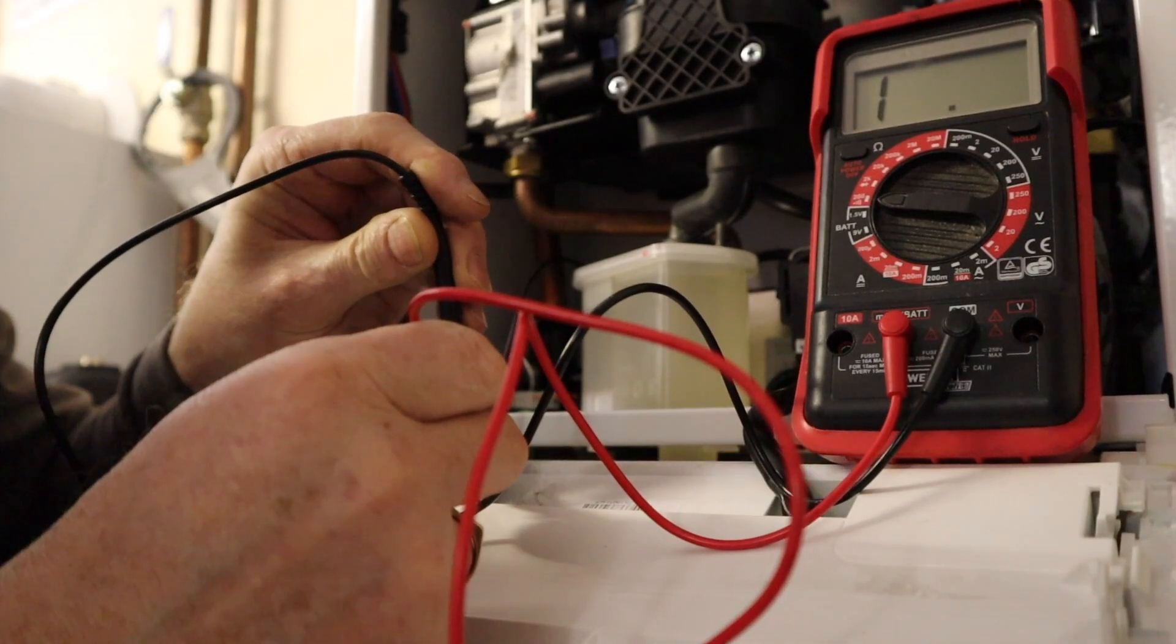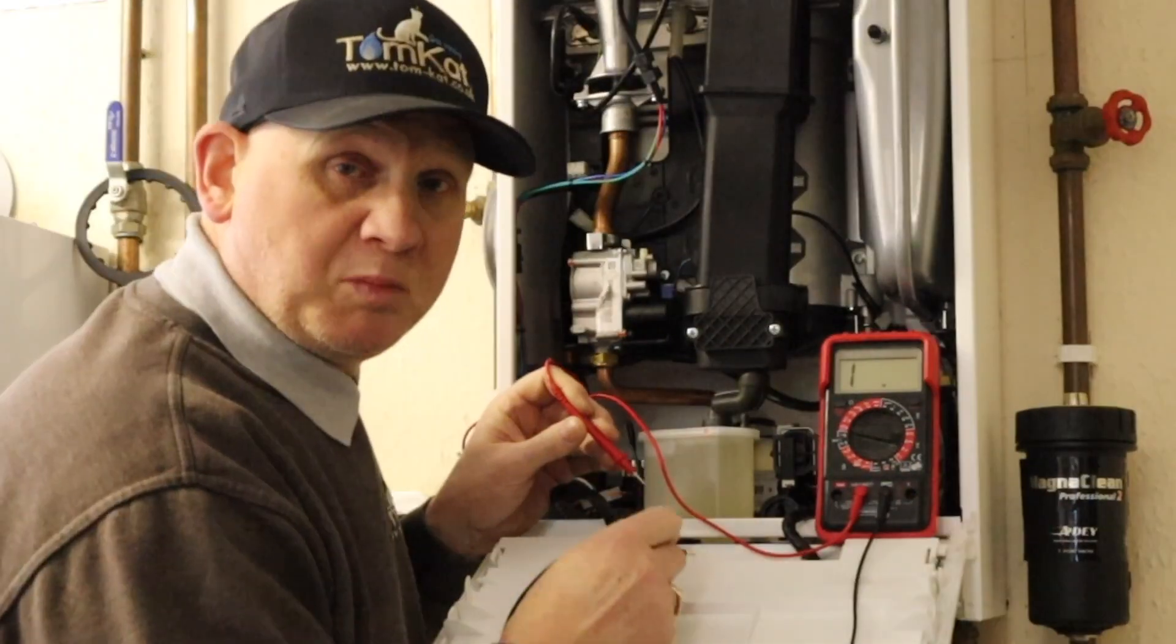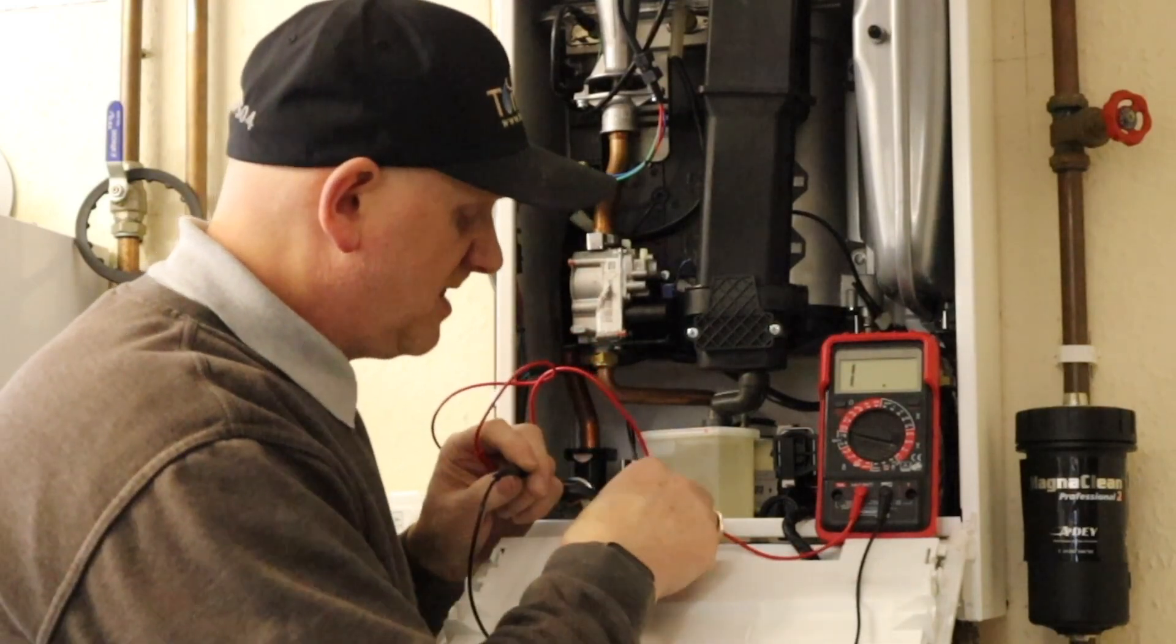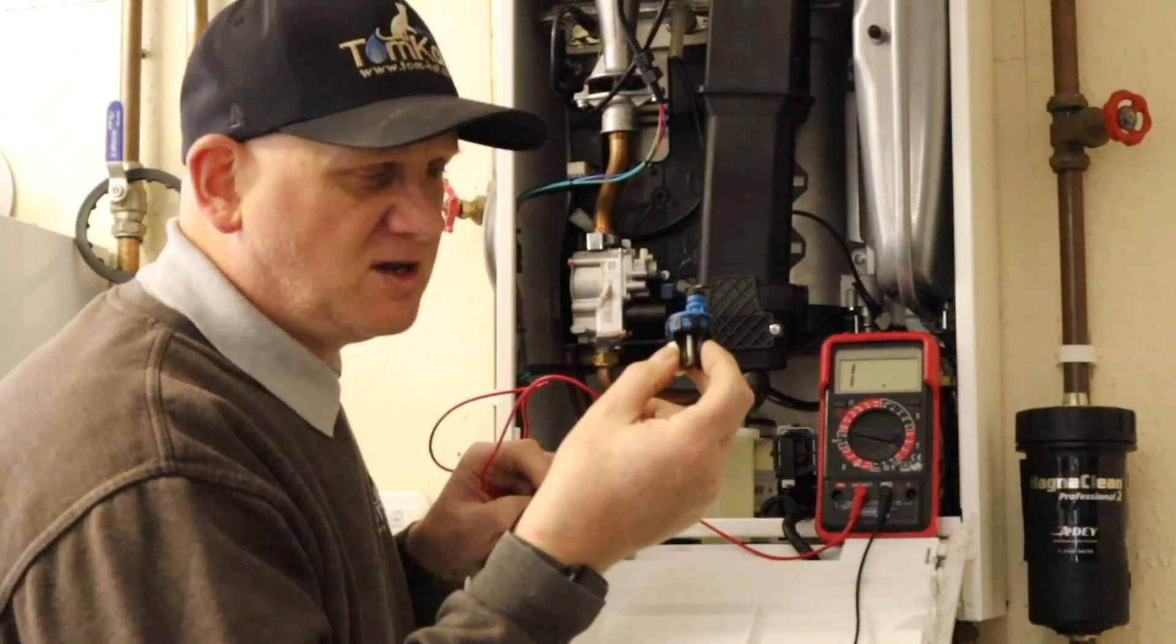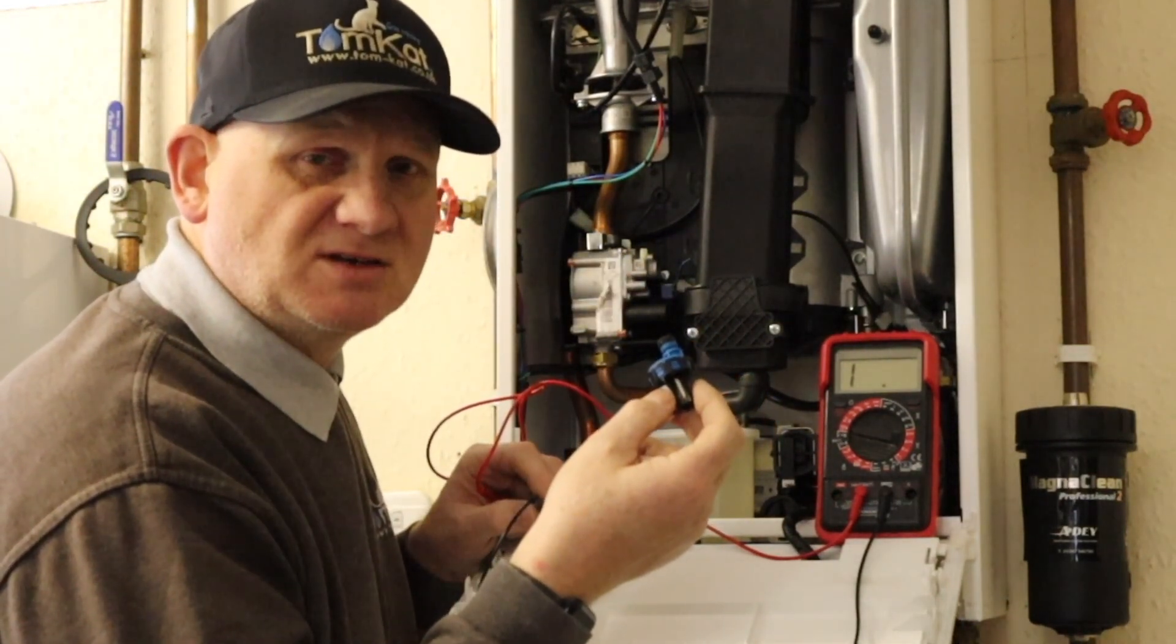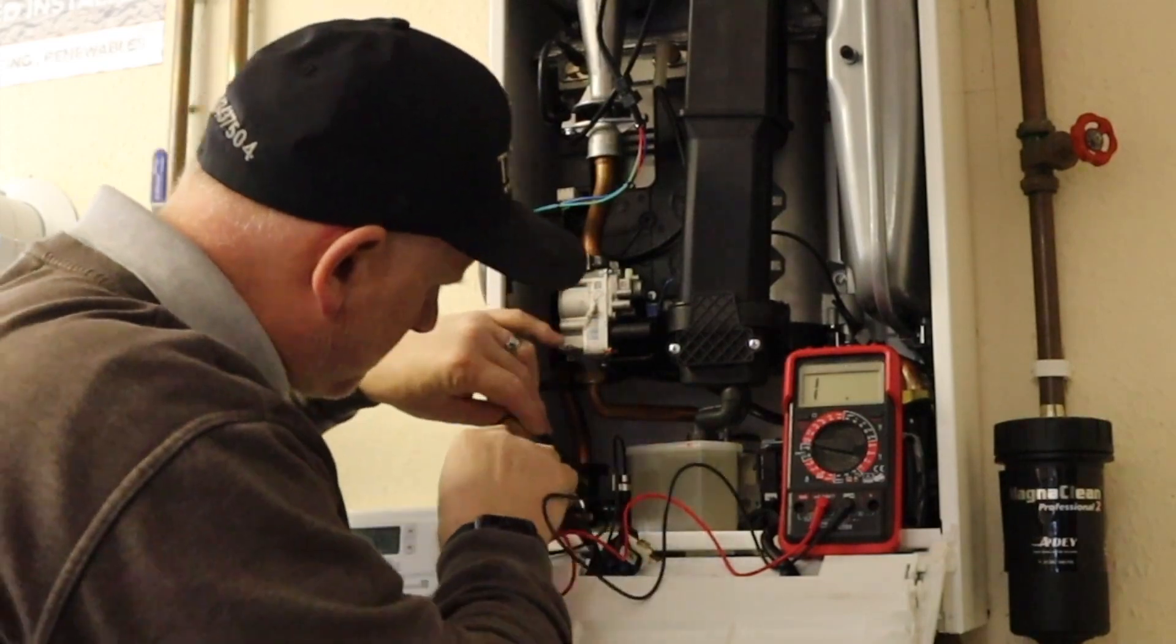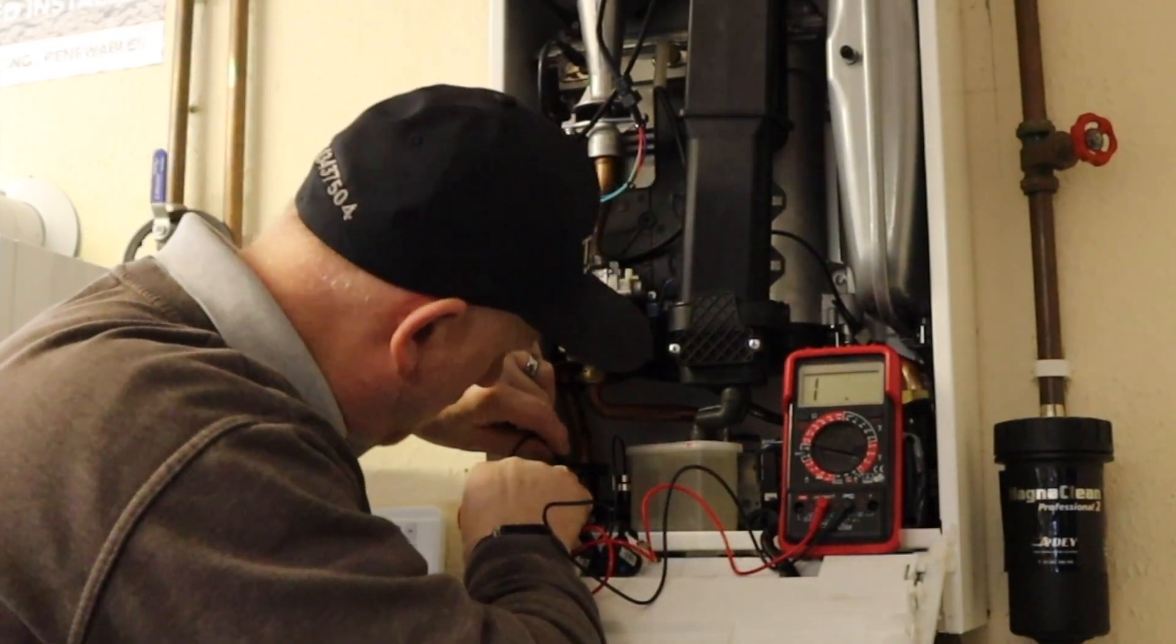But if you go on to the two connectors and you do actually get a reading, that means this is stuck in the closed position. So the boiler thinks there's water in there and there actually isn't. Now obviously the power's off on this boiler. If I remove these two cables and do the same thing on here, we should get less than 1 ohm.